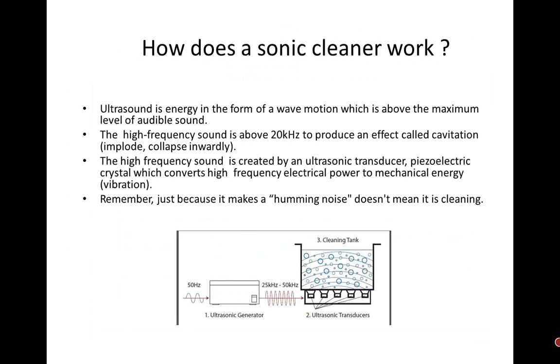A sonic cleaner works with energy in the form of wave motion, which is above our audible level. High frequency sound, above 20 kilohertz, produces an effect called cavitation. It implodes inwardly. The high frequency sound is created by the transducers, and then it goes through the bath. And this here's one of the few diagrams. You plug it in, have a generator, takes that, puts it into the transducer, and goes through there.